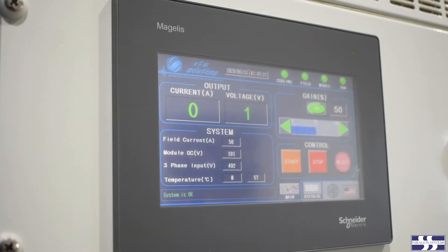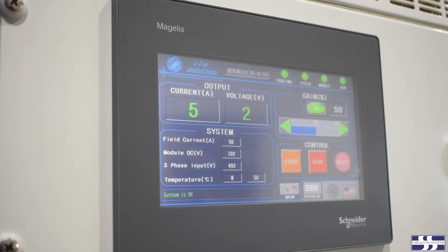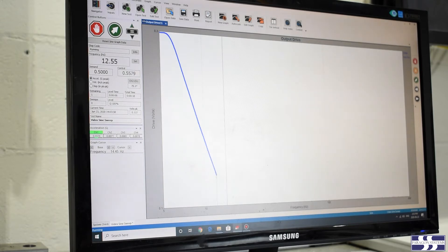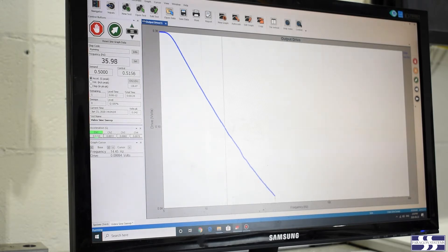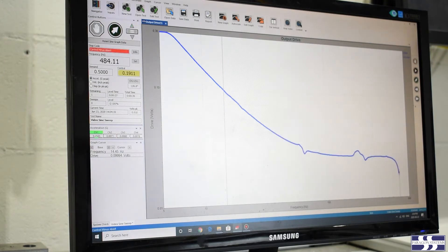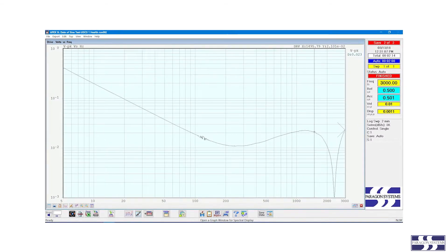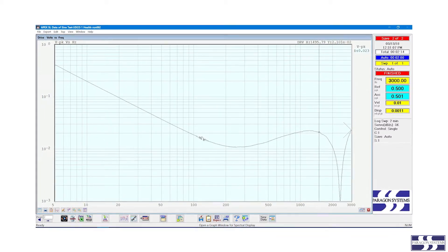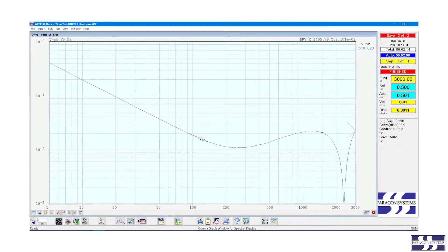An amplifier is rated for a maximum power output. This maximum power rating defines the maximum force which the actuator can impose on the static weight of the payload attached to the armature. The first important characteristic of an amplifier is that this maximum power is not evenly available throughout the frequency range of the shaker, because the amplifier is not equally efficient at all frequencies. Especially at high power levels or when testing with large payloads, the vibration test engineer must consider this frequency-related inefficiency when determining if the vibration system will be capable of performing your test.